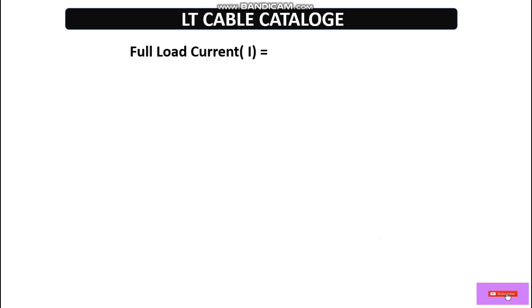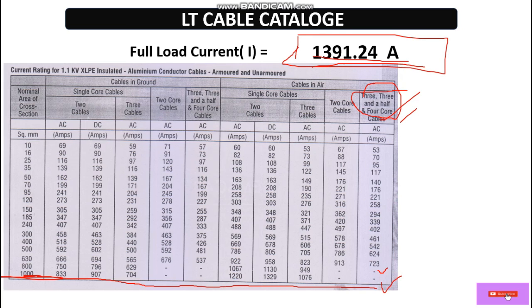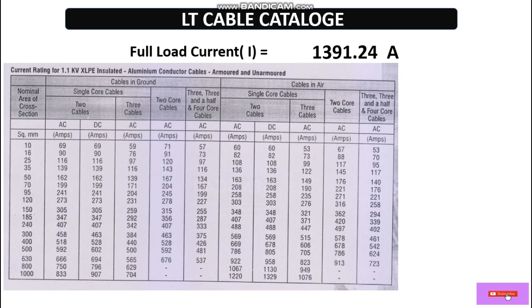Now we have calculated the full load current. We need to select a cable from the catalog for 1391.24 ampere. Looking at the cable catalog, this much current cannot be found in a single cable. The maximum cable size here is 1000 square mm, and looking at the 3.5 core or 4 core cables laid in air or in ground, we can only find up to 723 ampere capacity. So we need to increase the number of cable runs.